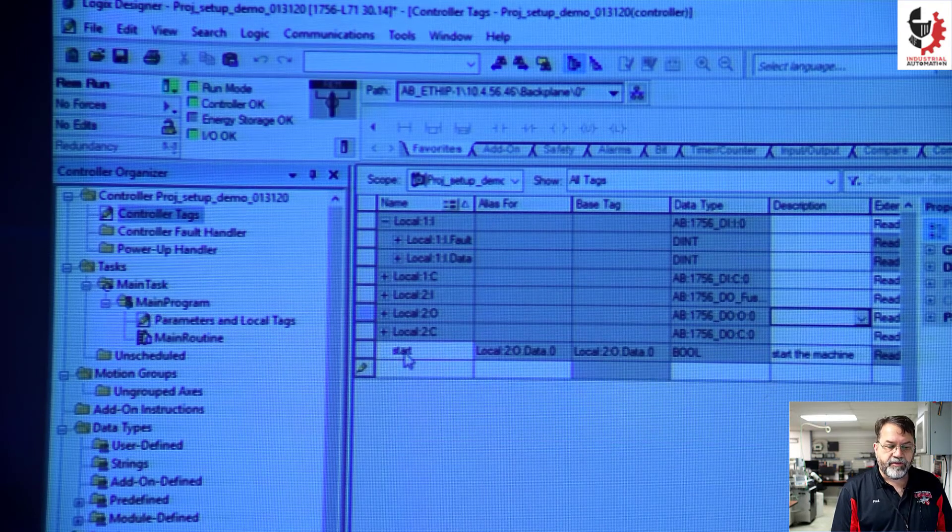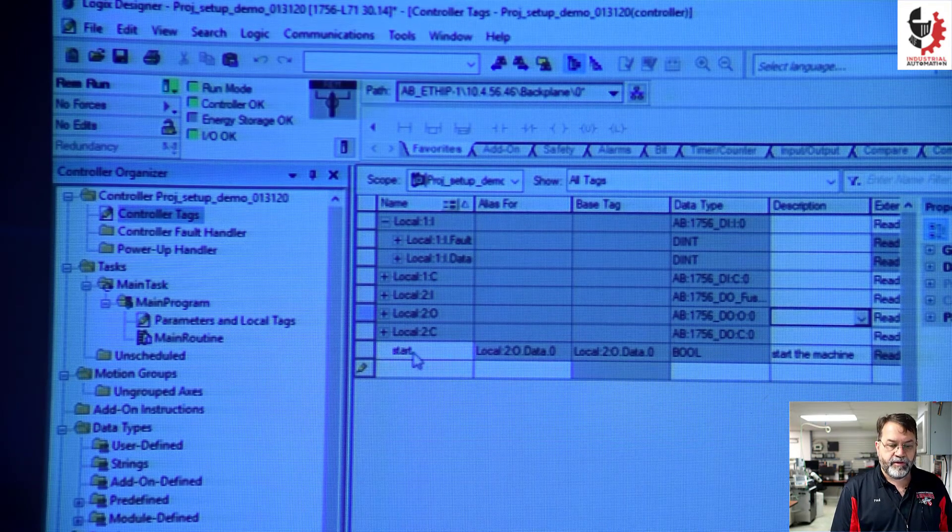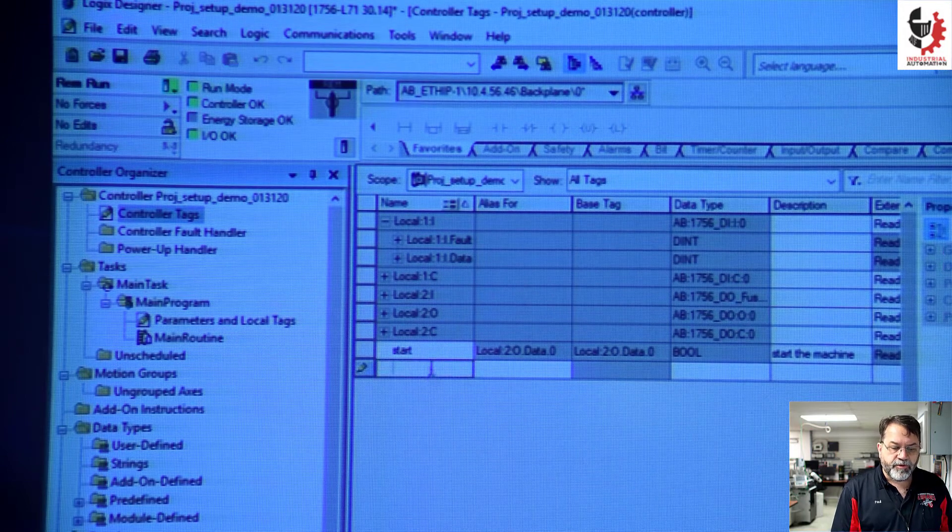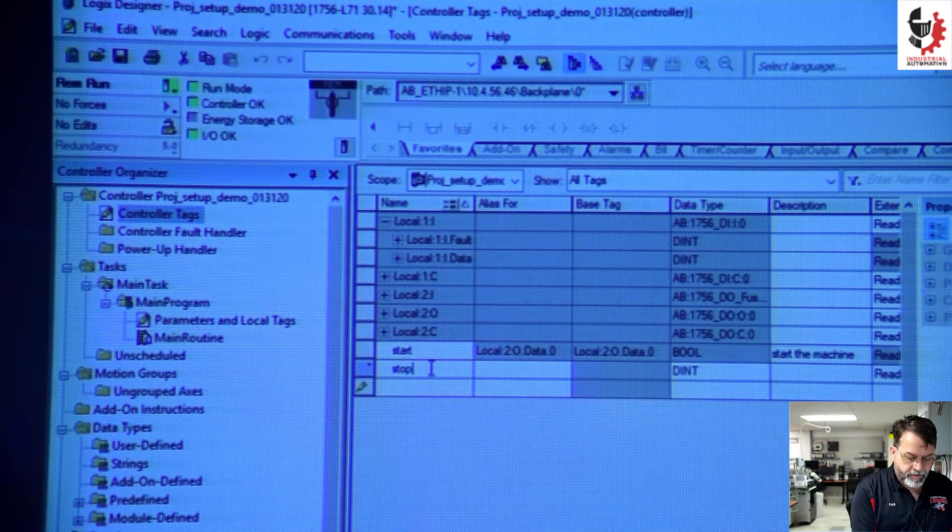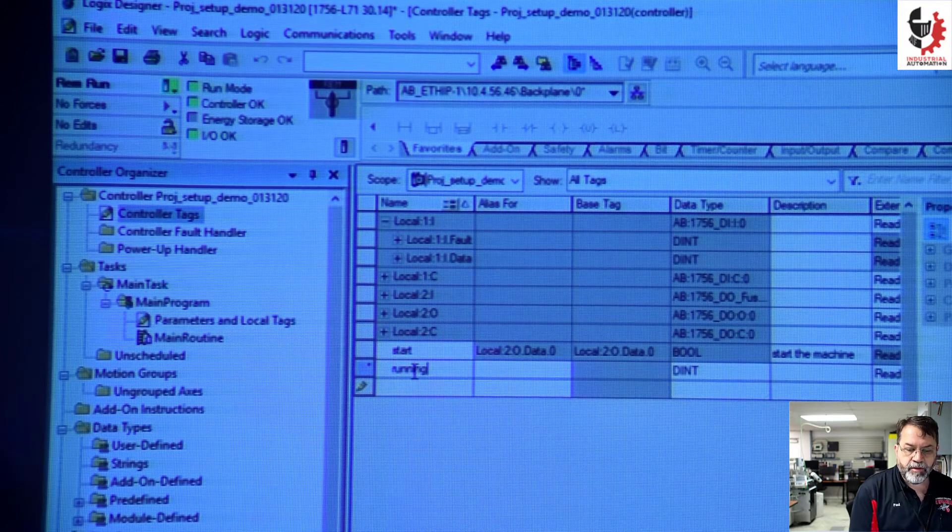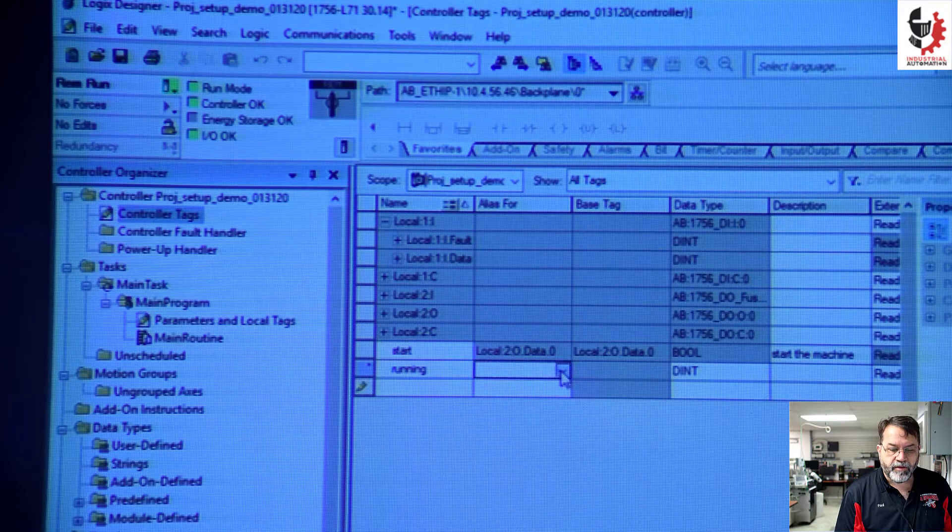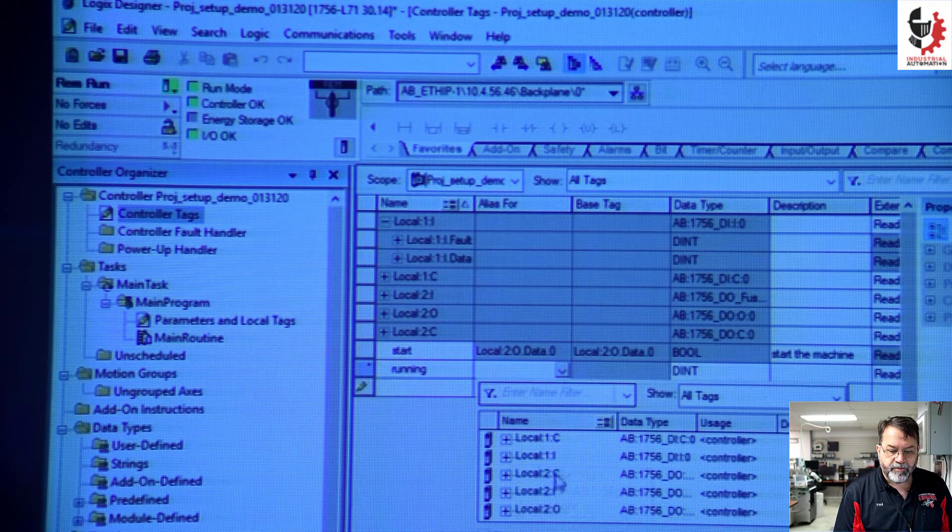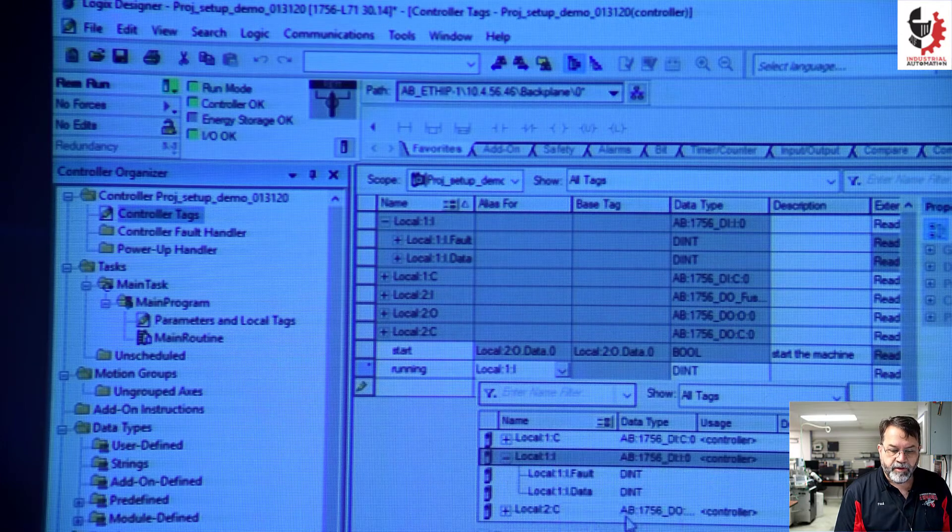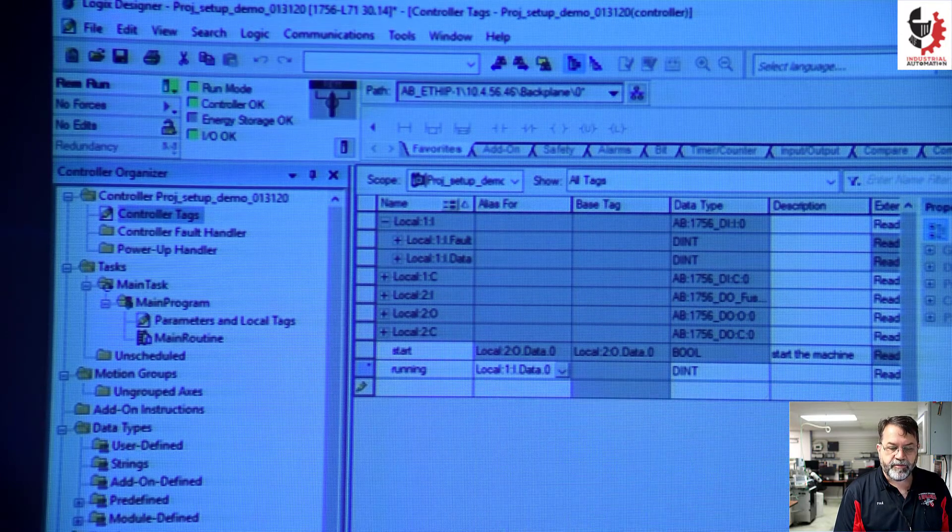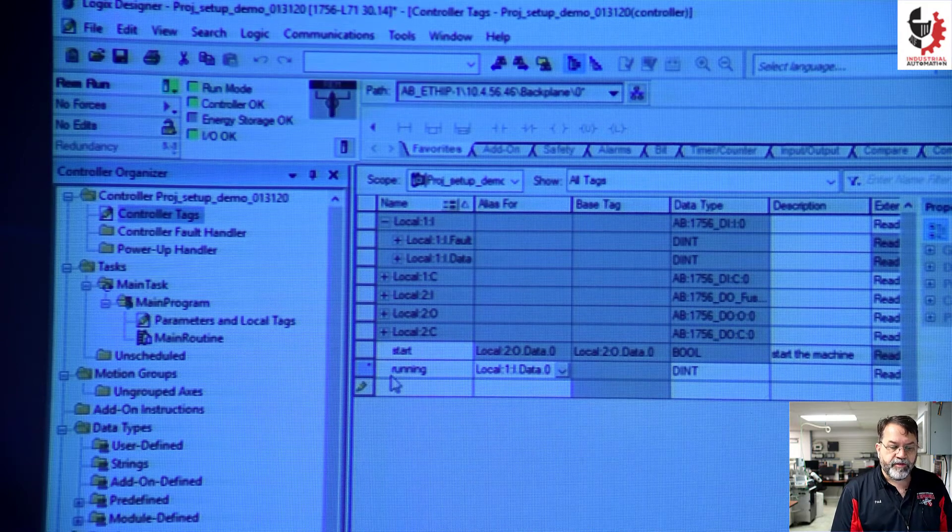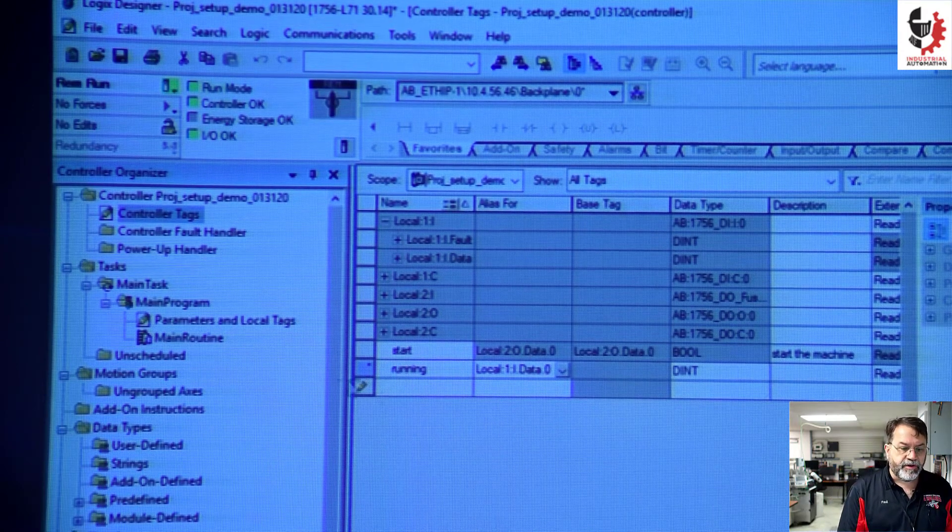Okay, so there's my start alias. I'm going to do one called running. And I'll link that to an input. So local one I for input. And I want to use the data and I'll use location zero. So now I have two tags. One is start and one is running. Those are both in my controller scope tags.